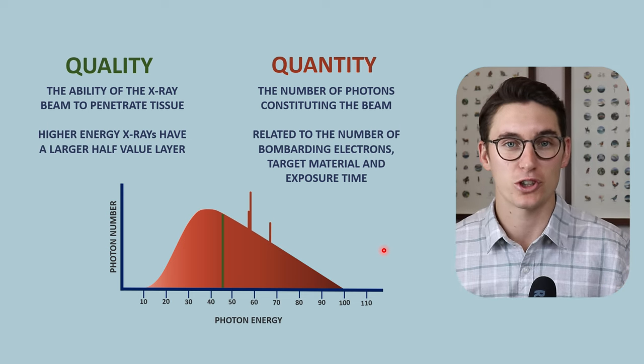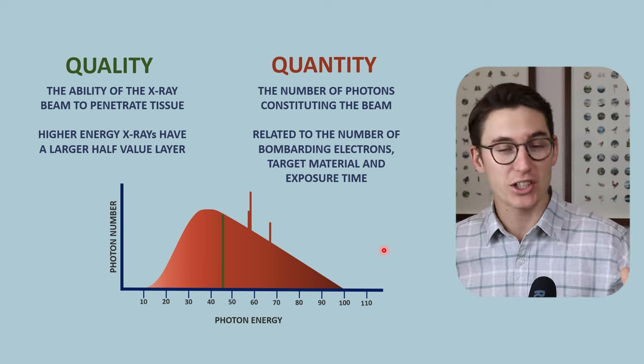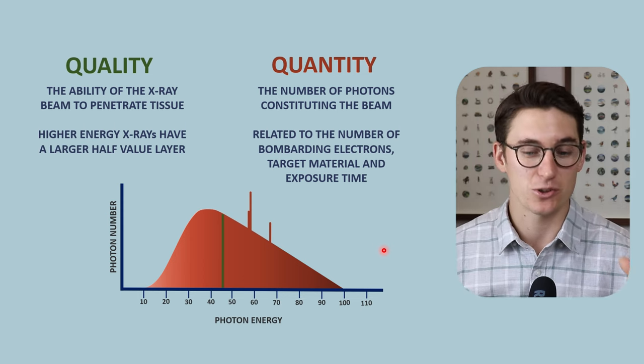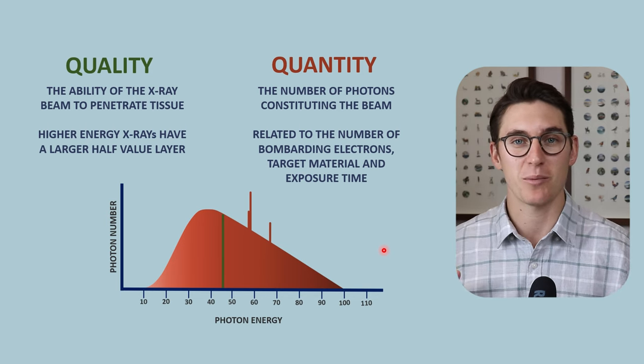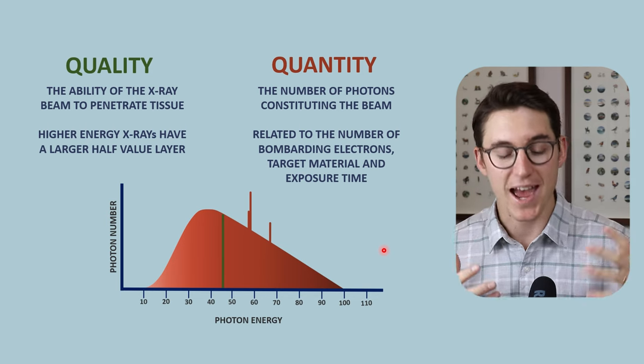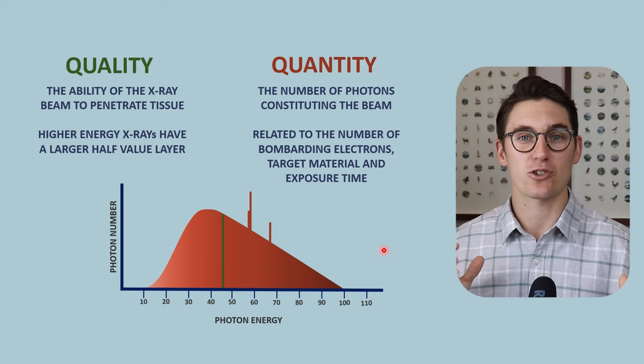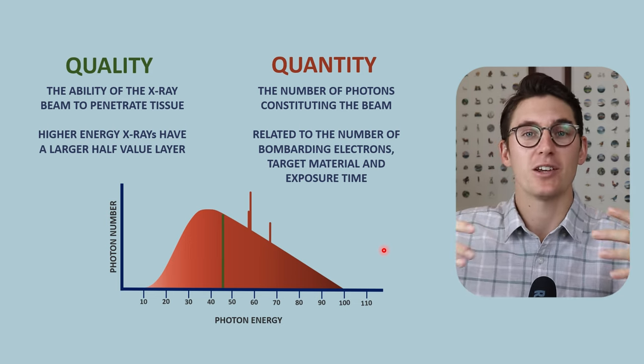We can manipulate the number of photons within the X-ray beam by changing the number of electrons that we accelerate towards our anode, by changing our target material - a higher atomic number will give us more X-rays - and we can expose the anode to electrons for a longer period of time, giving more X-rays.